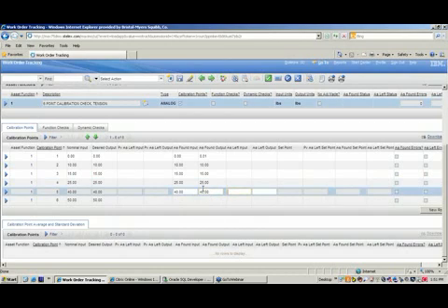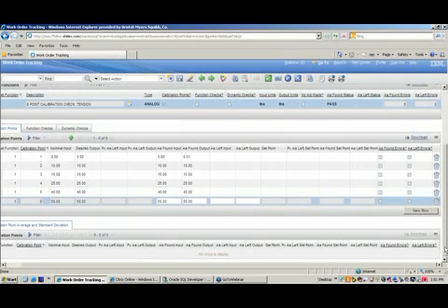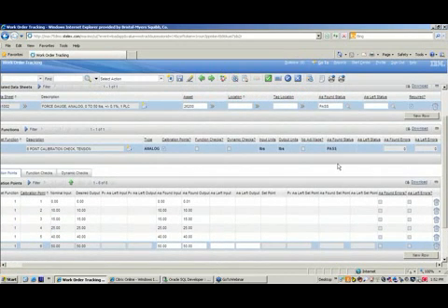In some places, this is done on paper. Hank's doing this directly electronically, but at some clients, they'll print out a work order for calibration that will have this information already printed on it in a table and row format, and they'll handwrite the values, and then someone will do the data entry. Some of our clients will use mobile technology, such as the Maximo work order management system, so you can capture it through a smart device or a laptop or a pad.